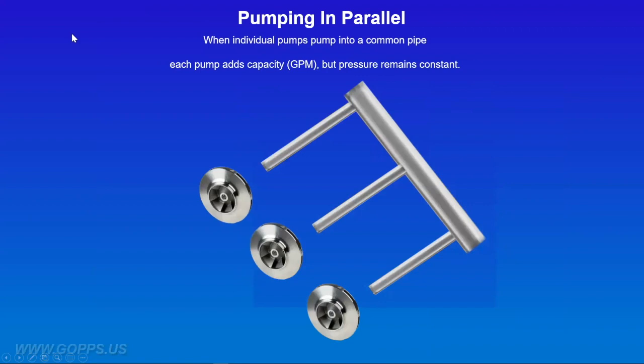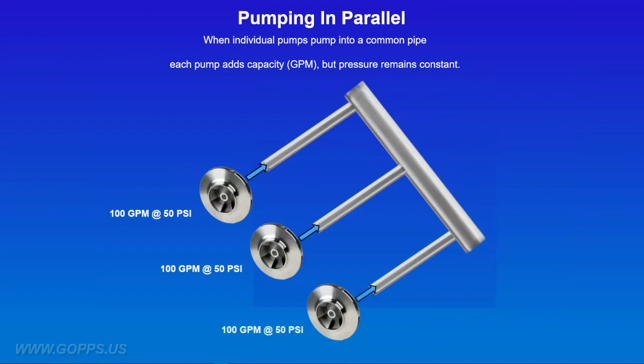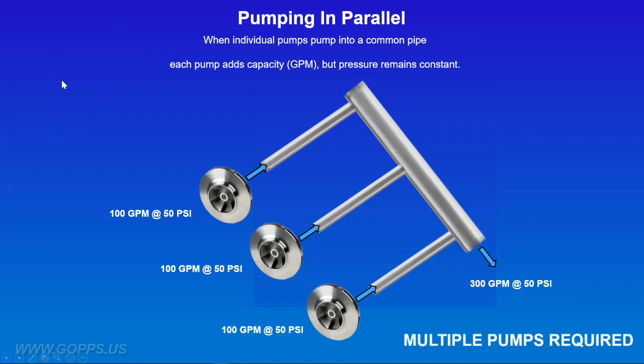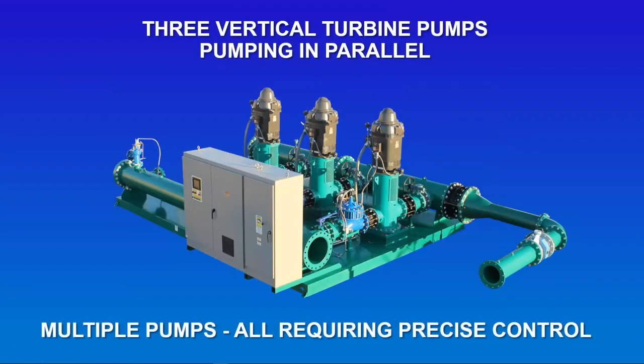When individual pumps pump into a common pipe — pumps in parallel — the result is the opposite of series: each pump adds capacity but pressure remains constant. The first pump puts 100 GPM at 50 PSI into the manifold; when the second comes on, it also adds 100 GPM at 50 PSI, and the third does the same. The output then is 300 GPM at 50 PSI. Each pump in a parallel configuration only produces part of the overall capacity, but multiple pumps are required.